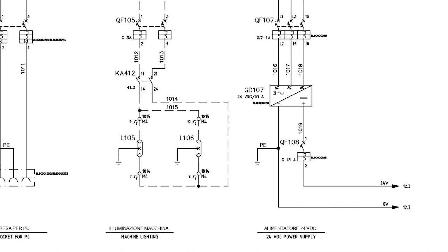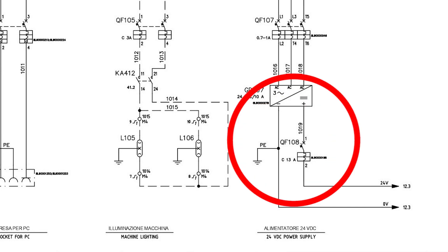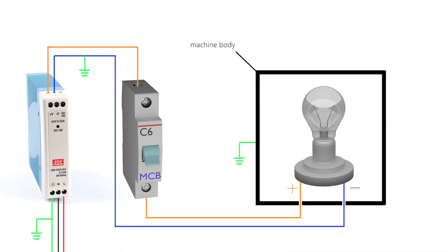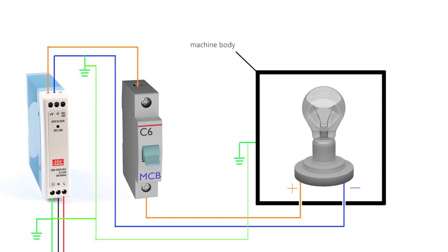One of my subscribers asked why we connect the negative DC wire to the ground earth terminal in the drawing. Let's look at a simple drawing with a DC power supply connected to a bulb inside a machine, with a wire breaker. The negative DC terminal is connected to ground, and the metal body of the machine is also connected to ground — all ground symbols are connected to each other via the ground wire. In normal conditions, current flows from the 24V DC terminal through the breaker, through the bulb, and back to the negative end of the power supply, completing the circuit and the bulb glows.